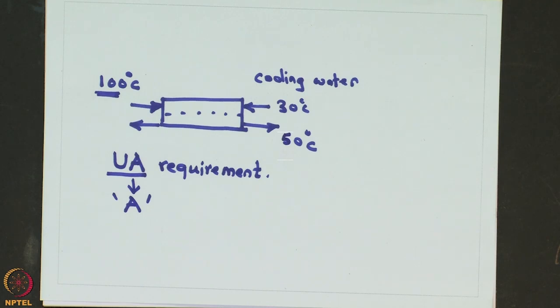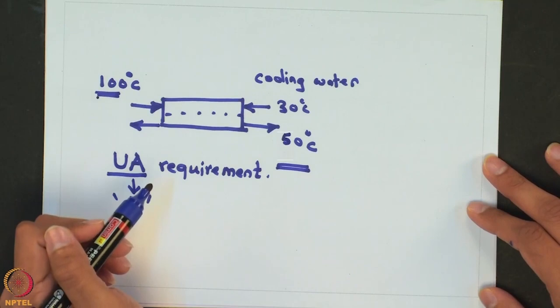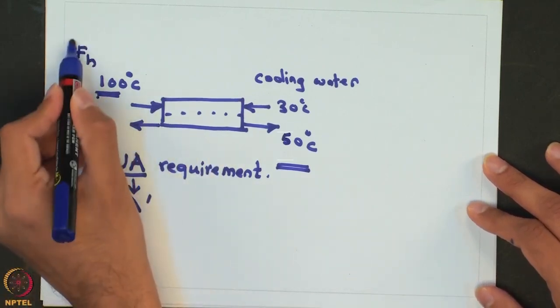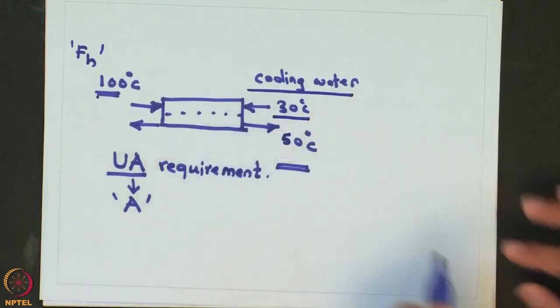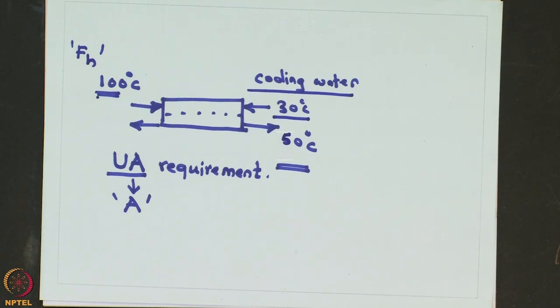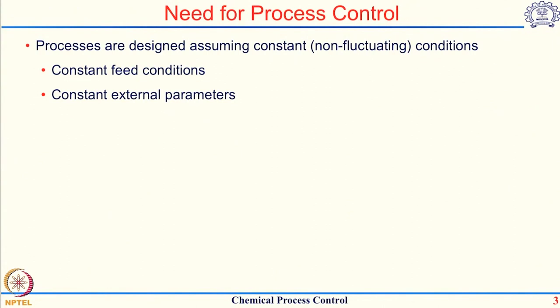Now, if you put that exchanger in a real plant, would it always give 50°C as the outlet of the hot stream? It will, provided your hot stream enters at 100°C, its flow rate remains constant at the design value, and the cooling water is available at 30°C. However, all these assumptions are not always maintainable when the plant is actually operated. When you design a plant you always design it at constant properties such as feed conditions, feed temperature, flow rate, feed composition, and external parameters like cooling water temperature. When you operate the plant, the operation is quite dynamic and is subjected to various disturbances.